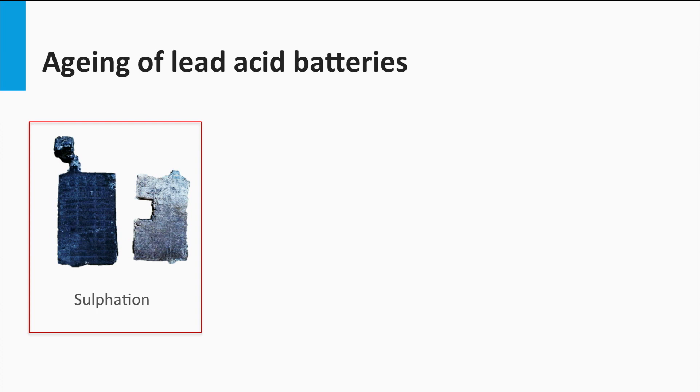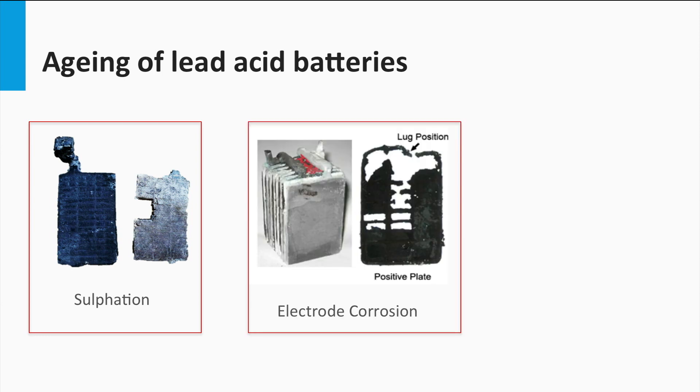Sulfation is one of the major causes of aging. Insufficient recharge after discharges causes sulfate crystals to grow, which cannot be completely transformed back into lead or lead oxide. Thus the battery slowly loses its active material mass and therefore its discharge capacity. Corrosion of lead grid at the electrode is another common aging mechanism. This leads to increased grid resistance due to high positive potentials.